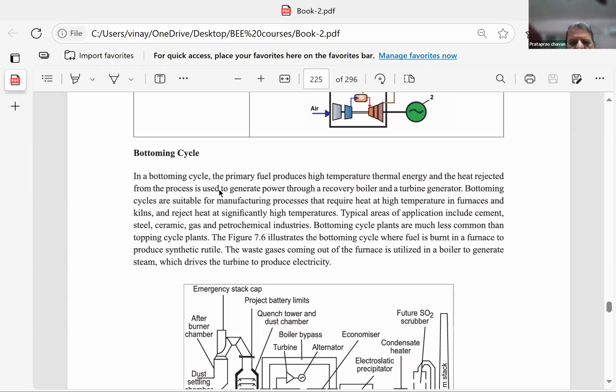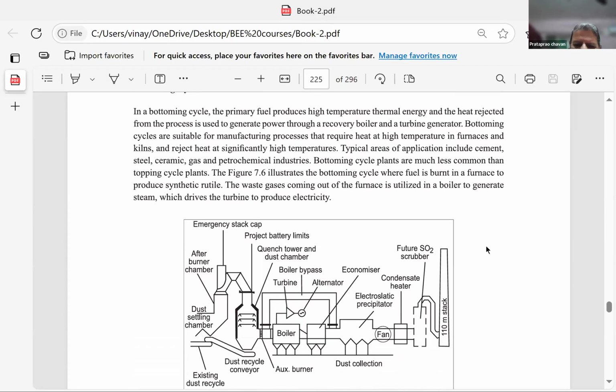Bottoming cycle examples are, for example, in cement industry or glass furnaces, where the temperatures required for the process are as high as 1000 degrees centigrade for melting the glass or roasting the gypsum and so on. After doing that work in the factory process, the exhaust of that furnace, which is at very high temperature - 700, 800 degrees centigrade - that exhaust is used for heating the water in the boiler.